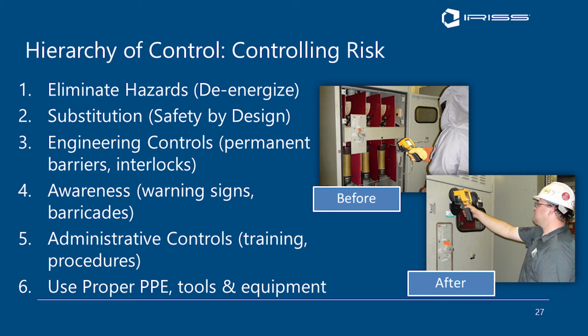And you're supposed to be on, I think it's a 5-year schedule, redoing your calculations for arc flash incident energy labeling and relabeling your equipment. That's baked into the 70E as well. So all of that is this awareness piece.